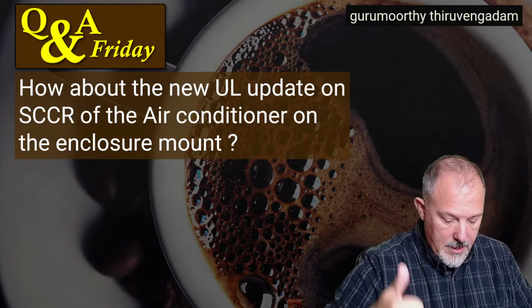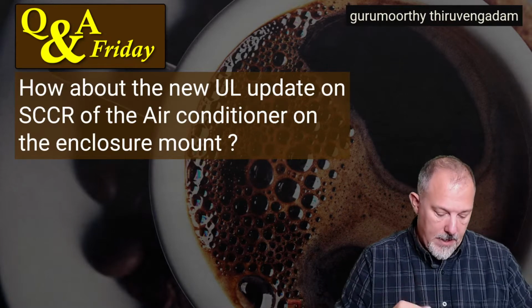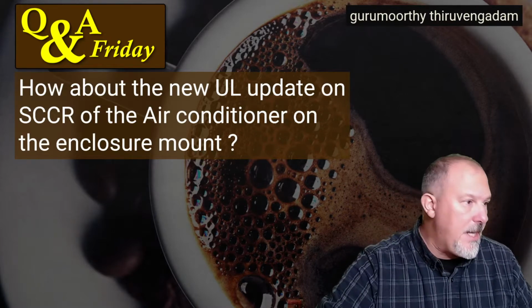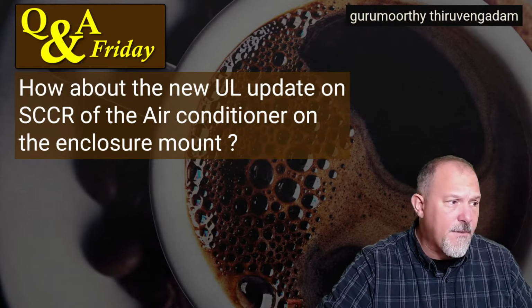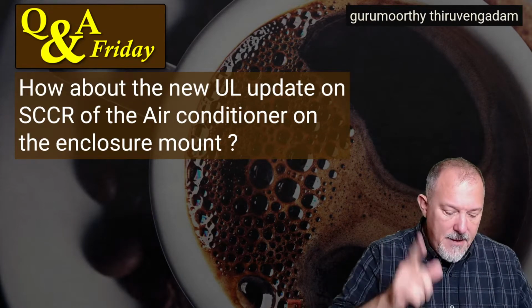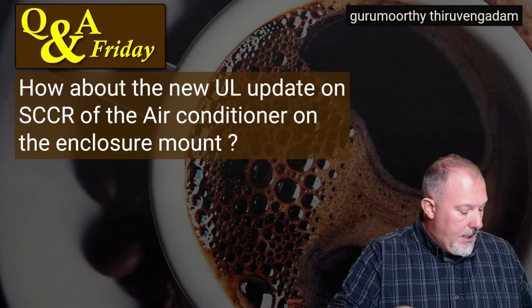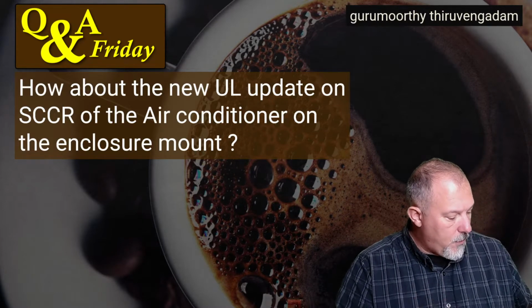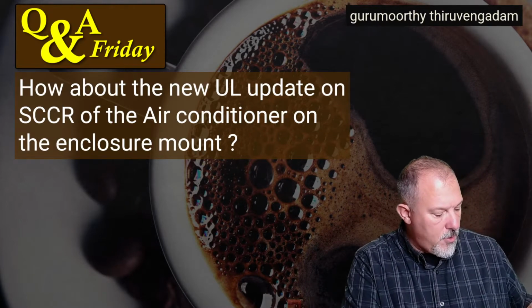SCCR, the marking of the short circuit current rating, is 440.4(B). I know that for a fact. And then in 440.10(B) in the National Electrical Code, there's where motor controllers.